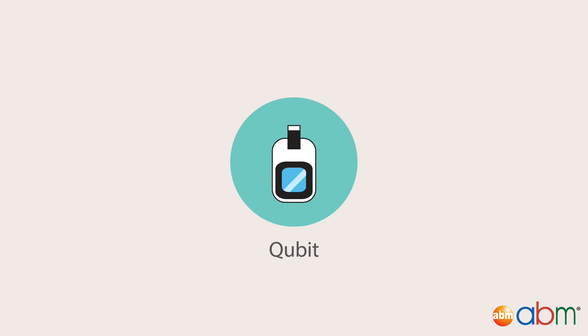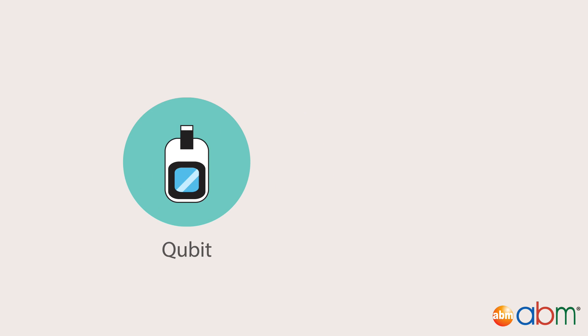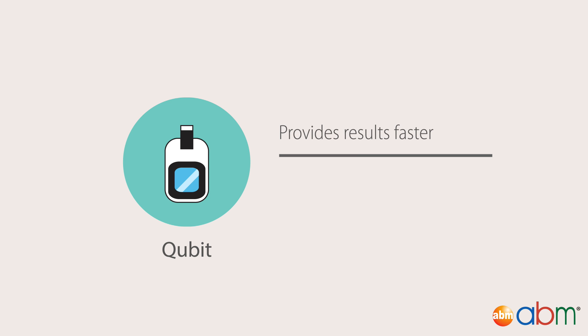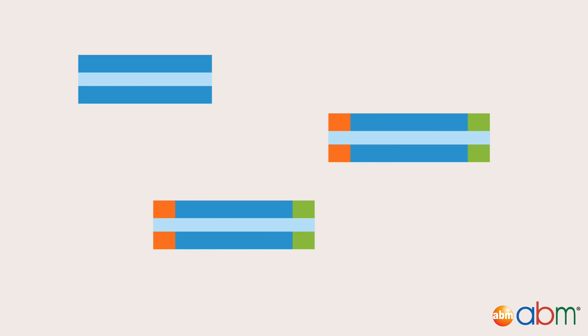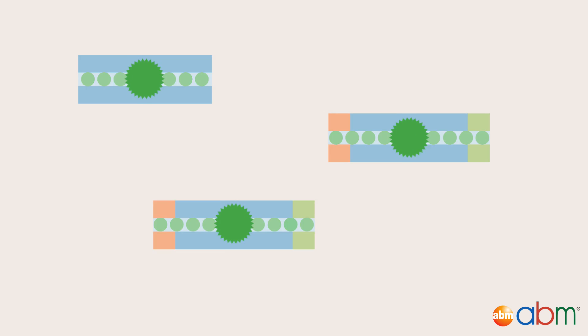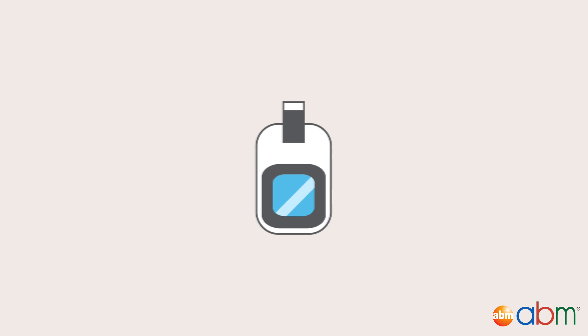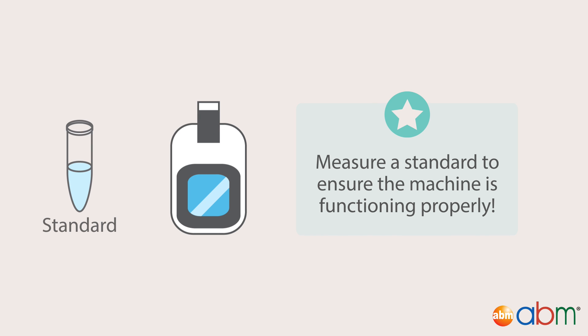Qubit is an alternative to qPCR for quantifying a sample library. Relative to qPCR, it provides results faster. However, it is not applicable for cases where there is no PCR enrichment, as it is less sensitive than qPCR and requires more sample. Quantification is performed by mixing the sample, which may be diluted, with the appropriate dye, which is then illuminated and detected by the machine. Note that a standard must be measured with the appropriate assay prior to sample quantification.